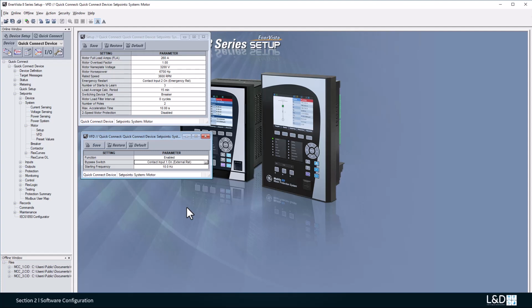When the bypass switch is closed, VFD bypassed operand is asserted or the function is disabled. Then the frequency source is switched from the current to voltage. All protection elements and metering work as normal. VFD setting will also affect the settings of the current unbalance 46, and we'll cover this later in the 46 element.